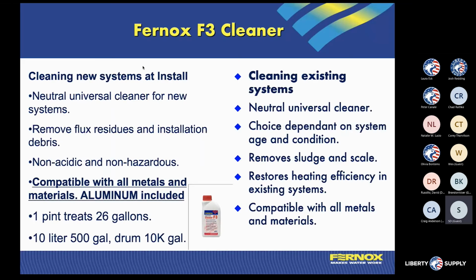So obviously the cleaner is the first step. If we're going to have a system that we are going to flush, we're going to add the cleaner. For every pint or every express can that we saw there, 1 equals 26 gallons. So for every 26 gallons of system fluid, I am going to install 1 of those cans. If we're on a commercial system, we also have a 2.5 gallon concentrate that you can put into a system or pour into a system. And that is going to do 500 gallons of system volume. So there are some relationships between how much product I use to the system size. That means we're going to have to go out to the system and calculate how many gallons.